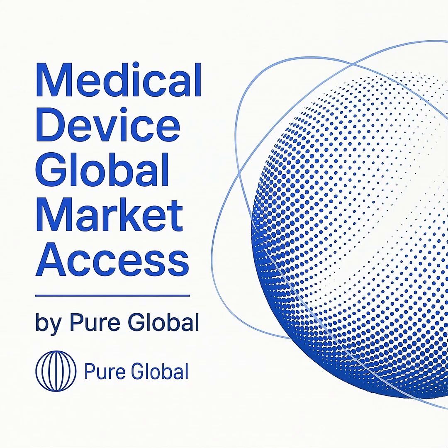In essence, ISO 13485 provides a foundational quality management system recognized globally. CE marking is the passport for EU market access, demonstrating compliance with rigorous EU regulations. FDA certification is essential for entering the U.S. market, with processes tailored to device risk. Manufacturers must also be aware that additional certifications may be necessary for other regions or specific device types. Adherence to these certifications not only builds trust and ensures regulatory acceptance, but is also fundamental for facilitating access to international markets. Navigating this complex global regulatory landscape can be a significant undertaking.